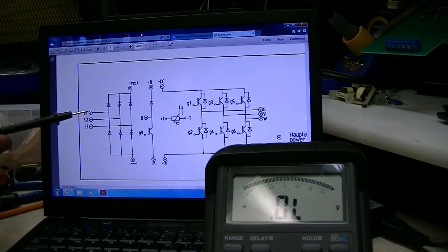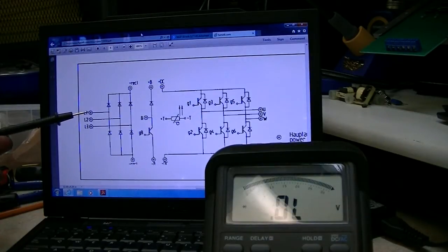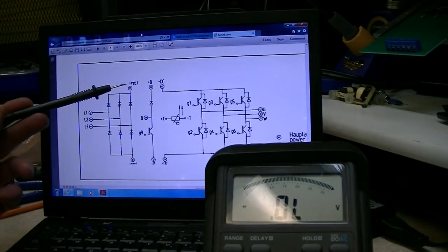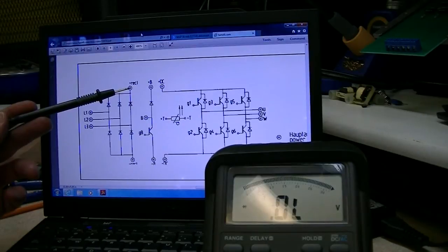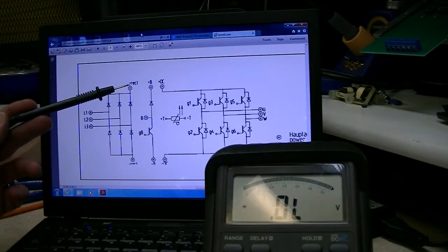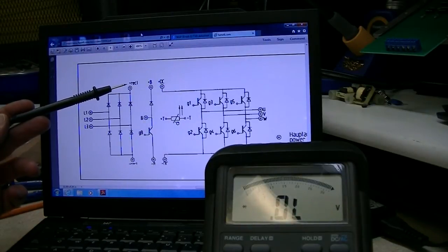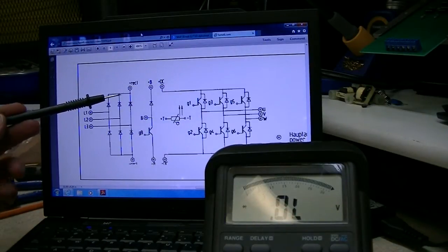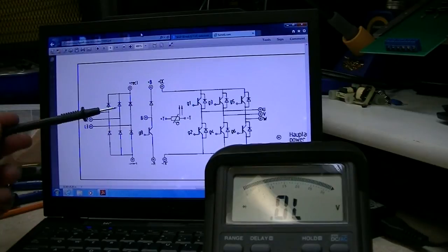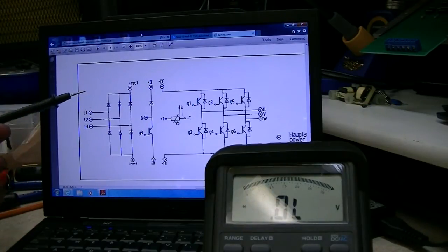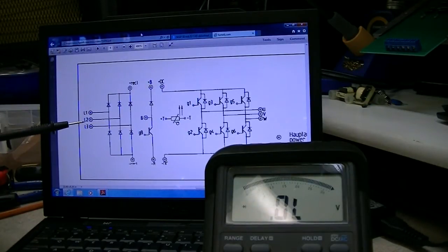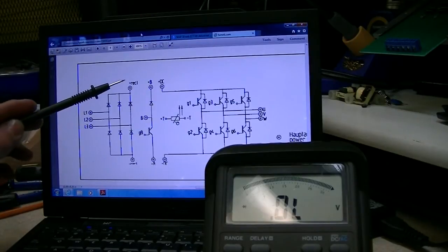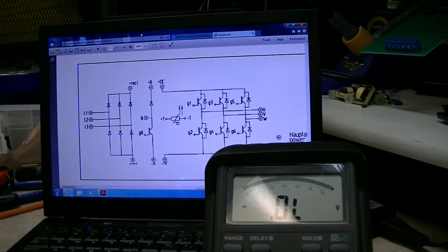So I'm going to use the diode function L1 to rectifier plus, I think that is. Like I said, this data sheet stinks. An awful lot of it's not very legible. Then I'll do the same thing L2 and then L3.